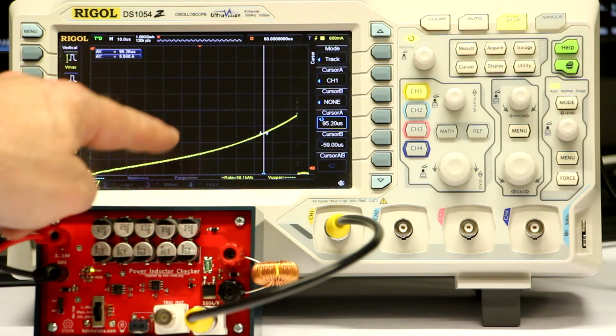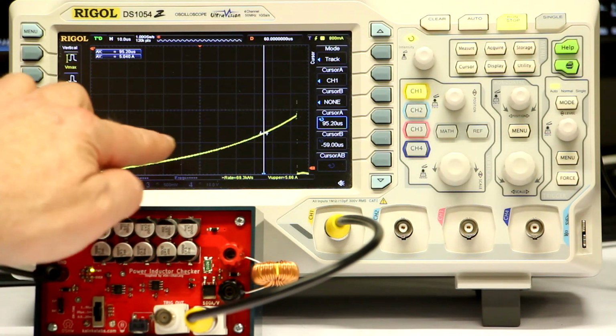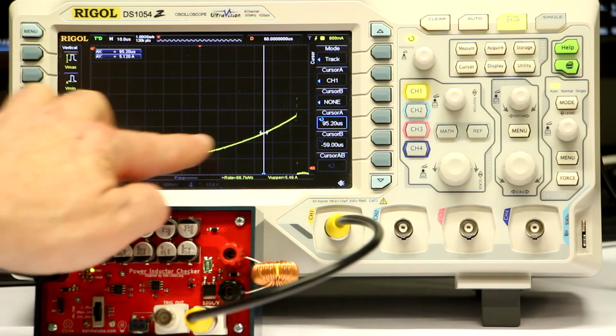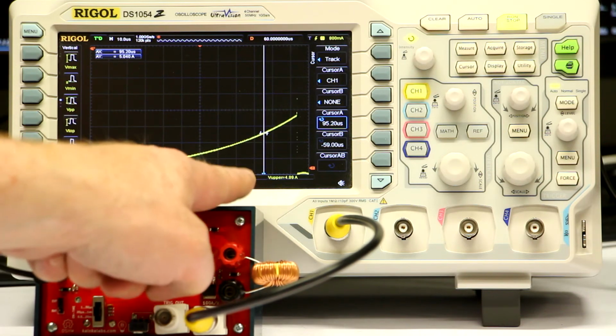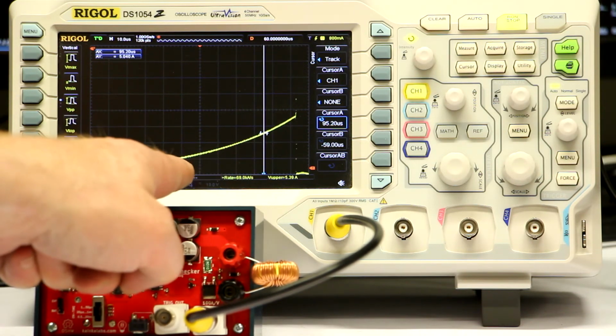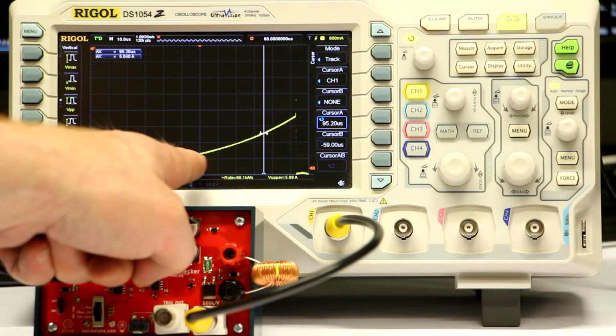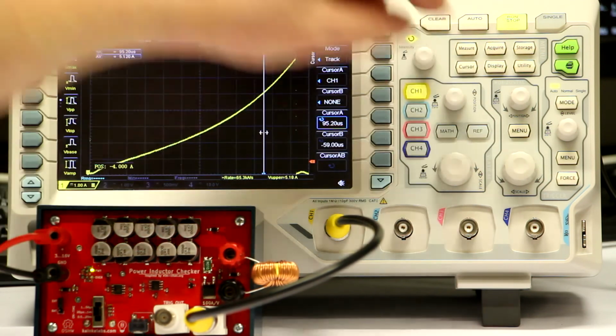We can also see that the point of saturation does not start at the rated current of 5 amps, but much lower, at around half of the rated current. So let's turn it back again.